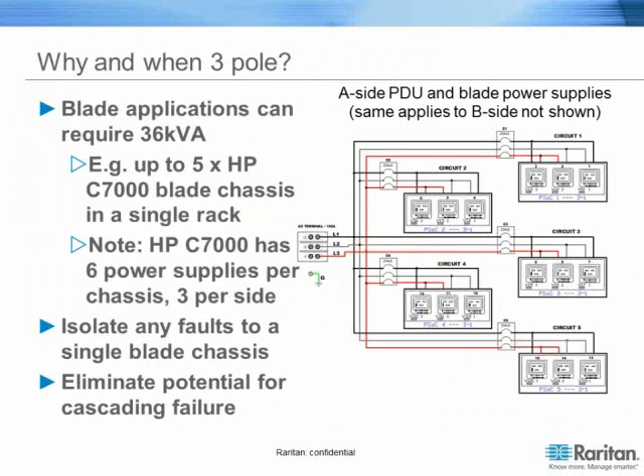In some instances, customers have requested a triple pole breaker, mostly utilized in blade deployments. Blade power supplies are very advanced. However, if they're not set up right, you have the capability that if one power supply goes down or trips, you can start a domino effect bringing whole blade chassis down. We've had some PDUs with a 3-pole breaker where each C19 plug is protected by its own 20 amp breaker. This is, I'll say, overkill, but let's make sure it's done properly.